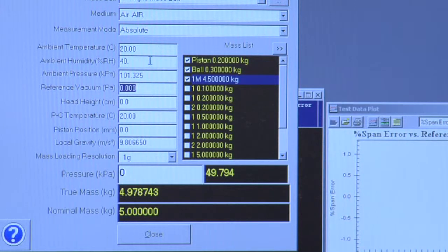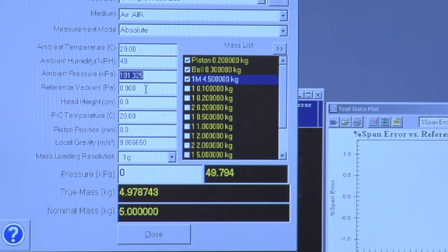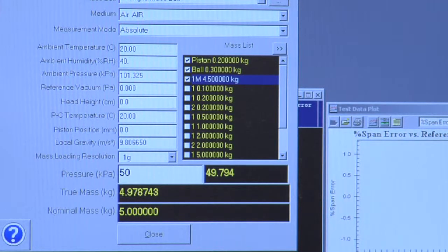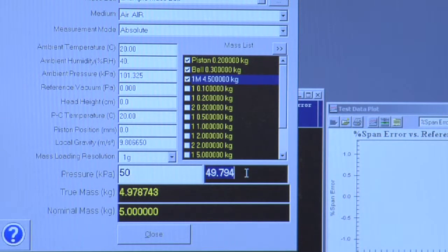Each of the characteristics that define the final pressure of the piston gauge can be entered manually in any one of these fields, or you can use another instrument to read those values automatically. In this case, if I enter 50 kilopascal and press enter, Compass will tell me the masses that I need to load to achieve this pressure.